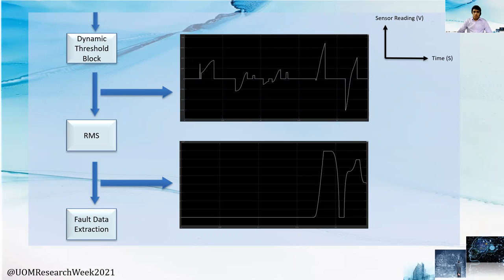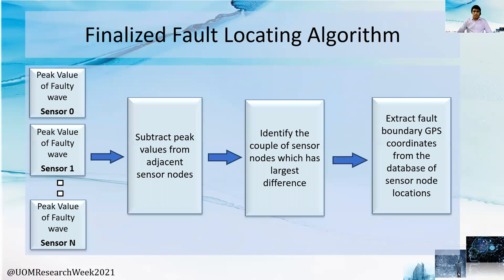It starts processing the incoming data to find its peak value, carried out for a given period of time which depends on the line protection device settings. This peak value is sent to the central server with the corresponding sensor ID. The fault locating algorithm is then executed using the peak values received from all sensors. It subtracts peak values from adjacent sensor nodes and identifies which adjacent sensor nodes have the highest variation in their peak values. These sensor nodes are determined as the boundaries of the fault, and the GPS coordinates of the fault boundaries are identified using a database of sensor IDs with their installed location data.